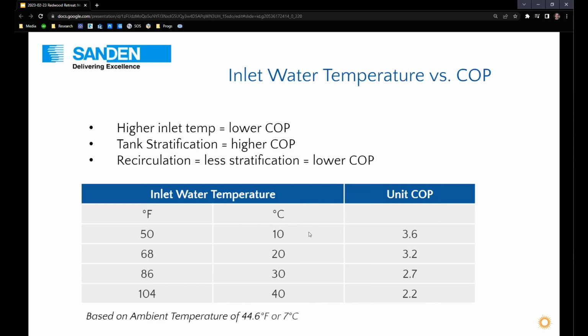Really low flow, like each Sanden moves 0.3 GPM, but it does a high lift. And when you disrupt that and you take recirculation water that's coming back at 100 degrees, it really screws it up. And actually, not just the efficiency, but also the capacity, meaning you can't deliver as much heat, and also the ability to heat up mid-temperature water. We found that by the time you get to 115, 120 degree return water, there may not be the minimum temperature to allow that heat pump to even turn on, right? Learned that lesson the hard way in 2017, and that's why we don't return recirculation to primary. We return it to a separate tank, because otherwise you can really get yourself into trouble.